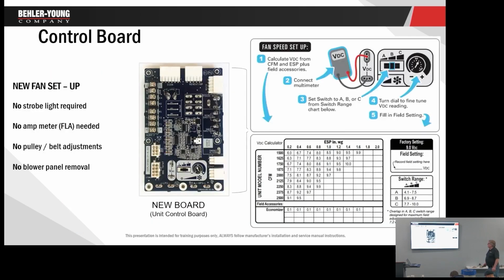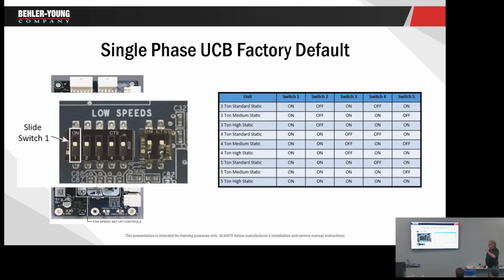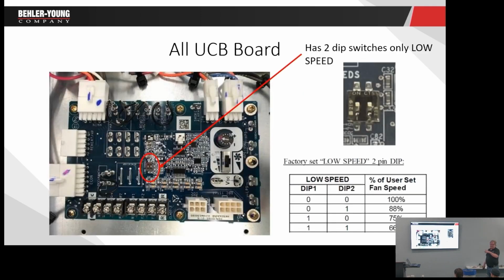Again, the first ones, make sure we put them back. These, we probably would put them back, but in the event we did want to eliminate that low speed circulation fan and go to high speed all the time, turn those both off. When you set a dip switch, you always have to cycle the power. If you flip the dip switch, it doesn't change anything until you cycle power. Shut the power off for at least a minute or 2 because we have to let the capacitors on the board discharge or the change won't take.